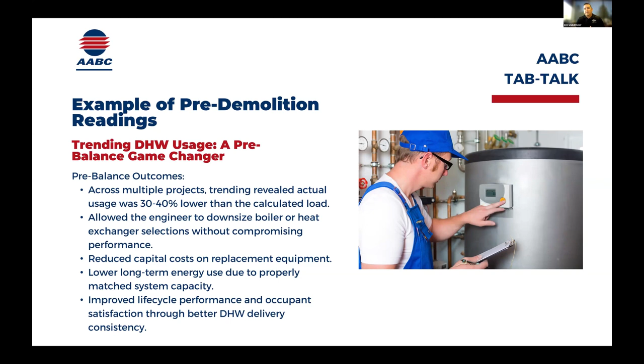Keep the end in mind. I talked a bit about this with the return air, but think like an engineer. If you're going out there to do pre-balance readings - and it's great that the notes were read - I go even beyond that: read all the notes and read the final balance. Where do they plan to get to at the end of this? Understand that you're taking pre-balance values right now, but where do they want to end up? What are those design values? Are they changing, are they adjusting? Are we reading now in our pre-balance that we're 200 CFM low from what the final balance is?